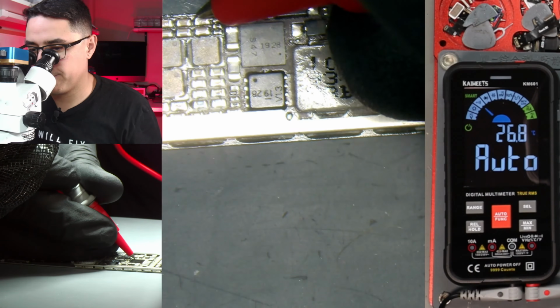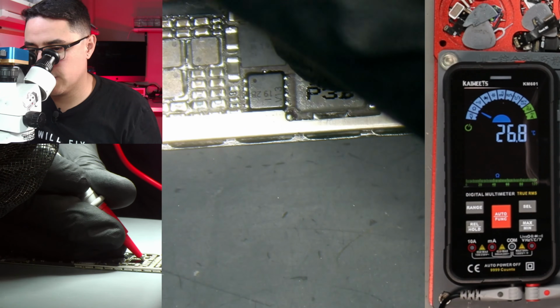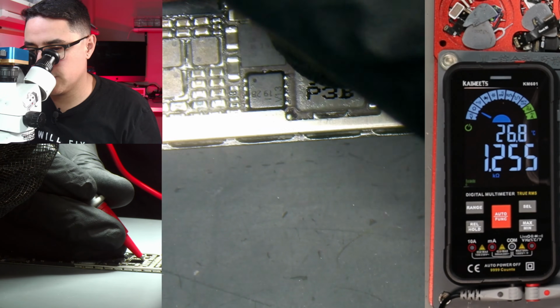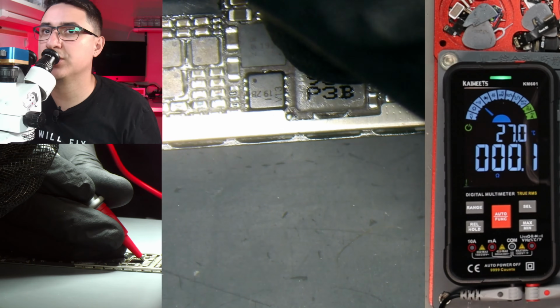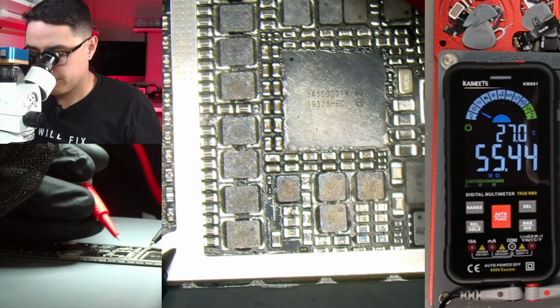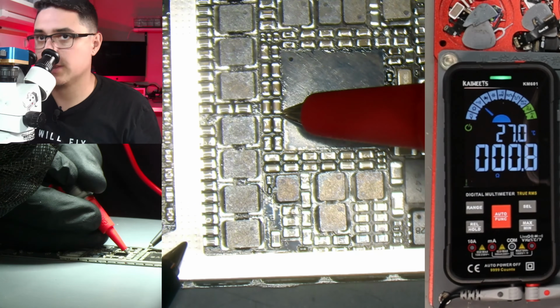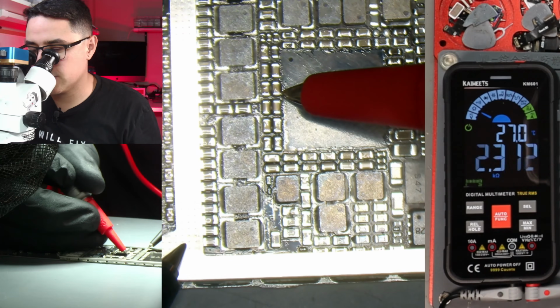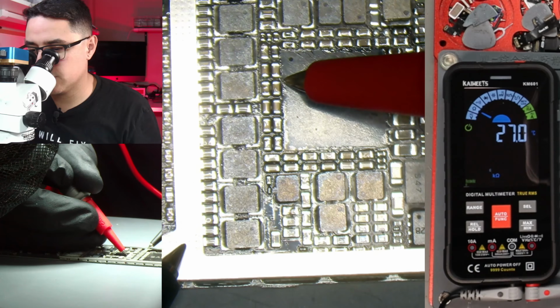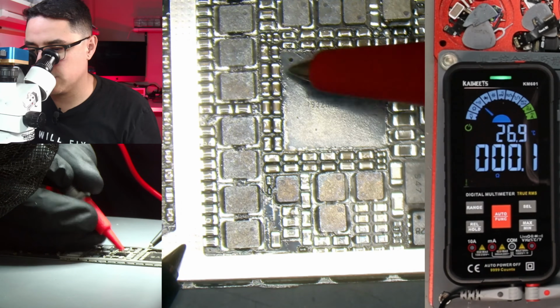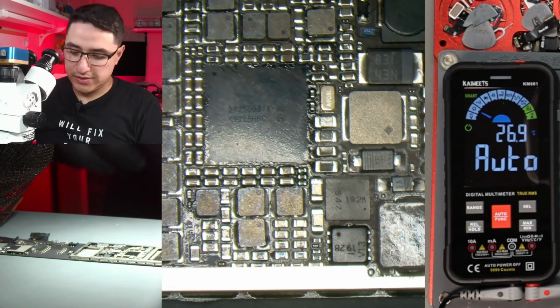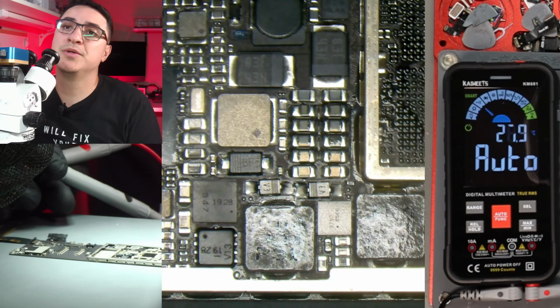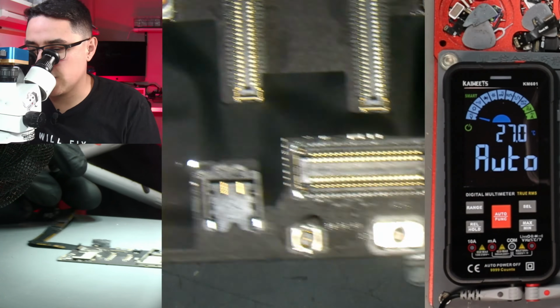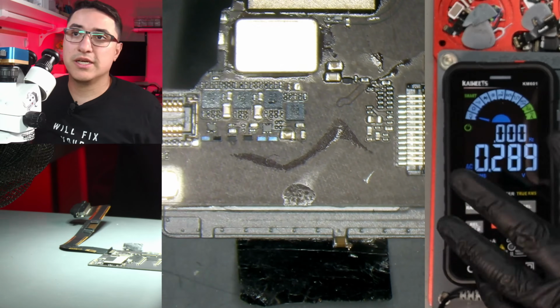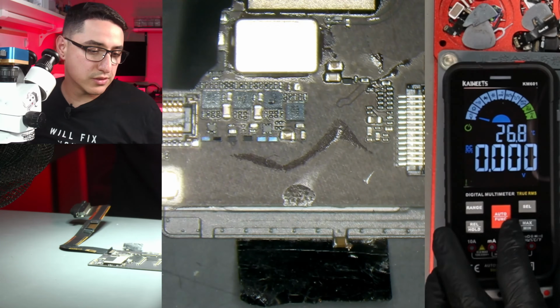So you just probe, any probe on ground, and then probe something. So that's not shorted, not shorted. So that's shorted, not this side. Well, not shorted, it just continuity to ground. So basically, you can probe stuff for shorts. So that has continuity to ground, but this side doesn't. This side ground, not ground, not ground, ground. So essentially, you use continuity mode to see if something's grounded. That's pretty much all you can do in continuity mode. You can't go any further in that diagnostics. Now, this is all done in auto mode, although you can manually switch between those modes yourself by clicking through them.